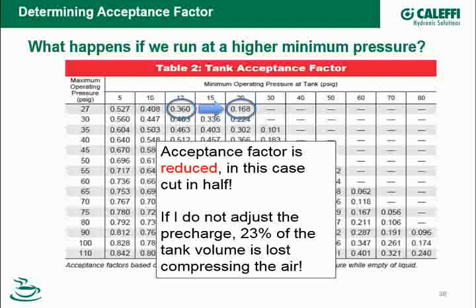The water goes in, it goes into the tank, and it compresses the air. Something that you should be aware of if you're doing it that way, compressing the air in the tank by bringing water in rather than just doing it with air, is that when I take that tank from 12 to 20 psi, I've just lost 23% of the tank volume, which is now holding water, because I've had to decrease the air volume by 23% to compress it up to 20 psi. So the point here is, if you're going to run at a higher pressure, make sure the tank is sized for that higher pressure. Otherwise you may run into issues where the tank that was sized properly at 12 psi all of a sudden is going to be too small when I get up around 20.